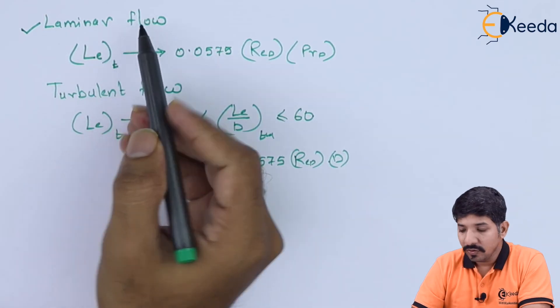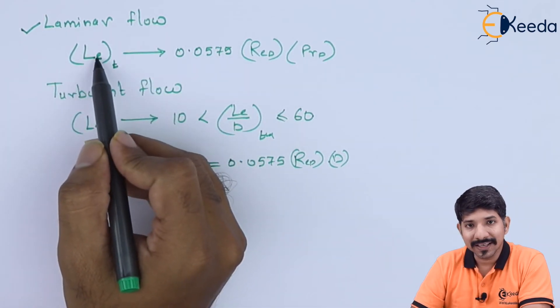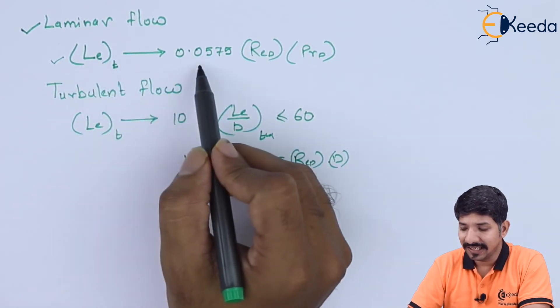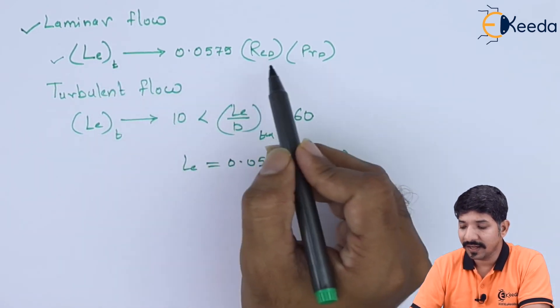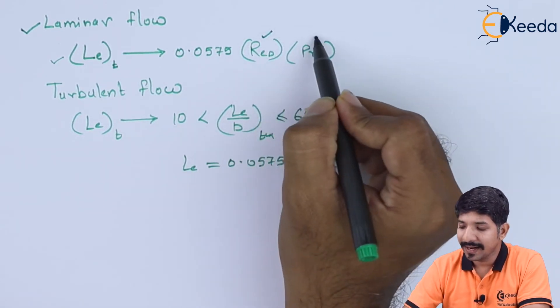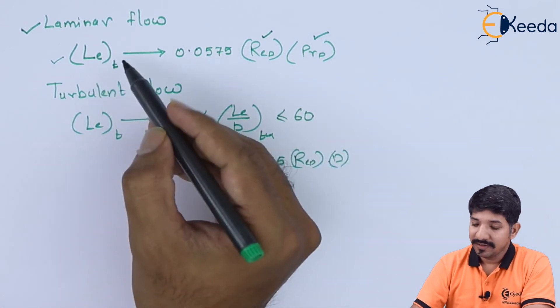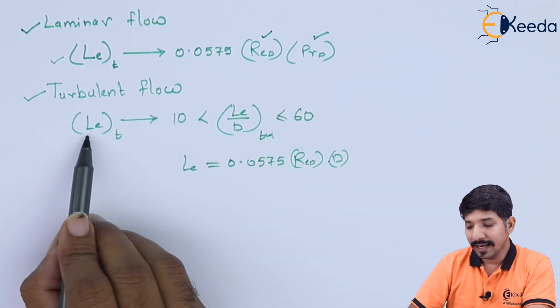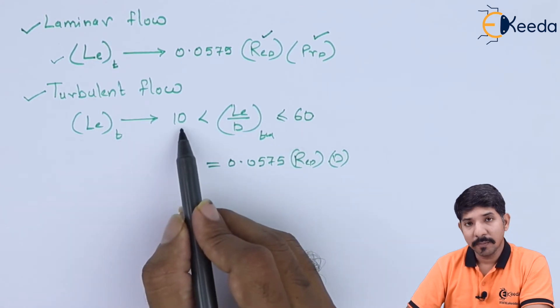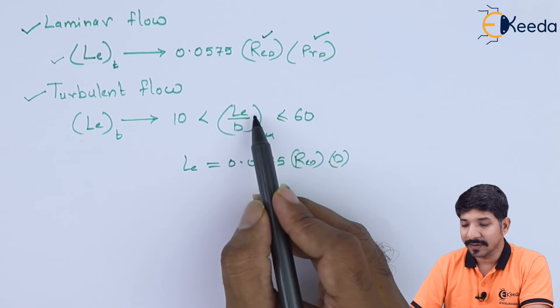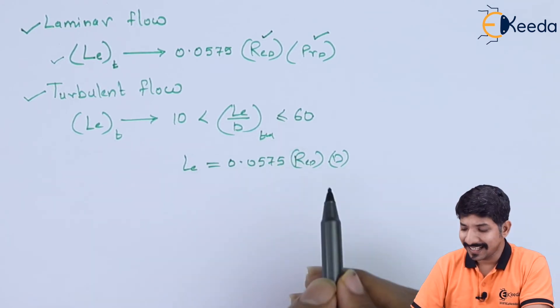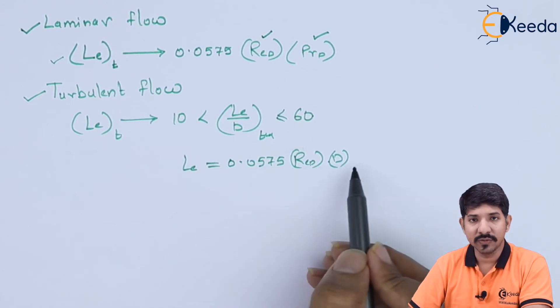If the flow is laminar, the length of the thermal entry region is given by the empirical relationship: L_e,t = 0.0575 × Re_D × Pr × D, where Re_D is the Reynolds number and Pr is the Prandtl number. For turbulent flow, when the ratio is between 10 and 60, the entry length is given as: L_e,t / D = 0.0575 × Re_D.